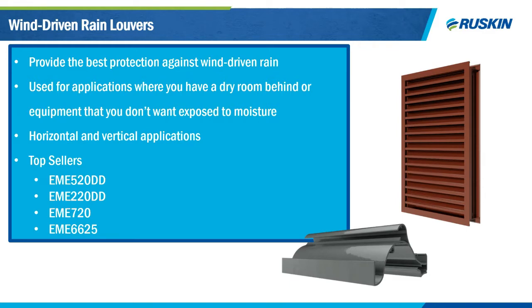Wind-driven rain louvers are available in both horizontal and vertical configurations with closer blade spacing, meaning they typically won't have the higher free areas of standard stationary louvers. Our top sellers are our 5-inch EME 520DD, our 2-inch EME 220DD — best in class for all thin line louvers — our 7-inch EME 720, and our vertical 6-inch EME 6625. The 520DD and 220DD typically sell the most but cap out at about 47% free area for the 5-inch. The EME 720 stands out by offering up to 56% free area, which most wind-driven rain louvers cannot offer.